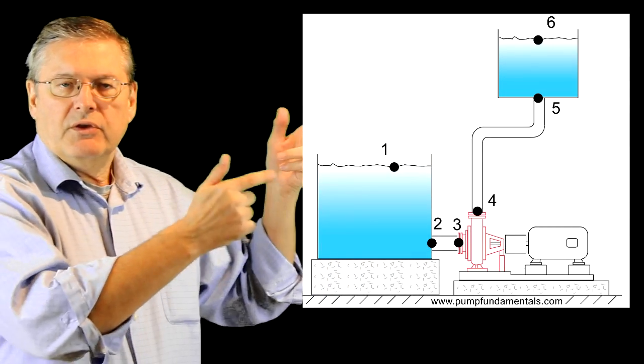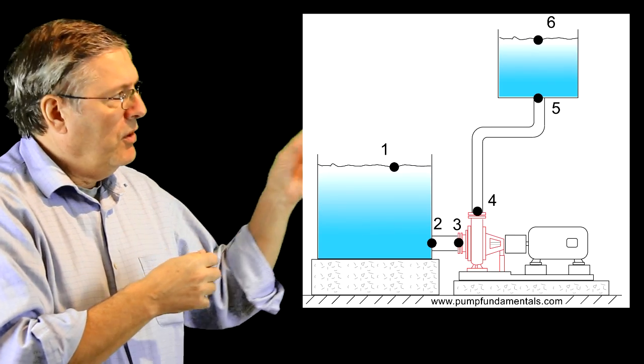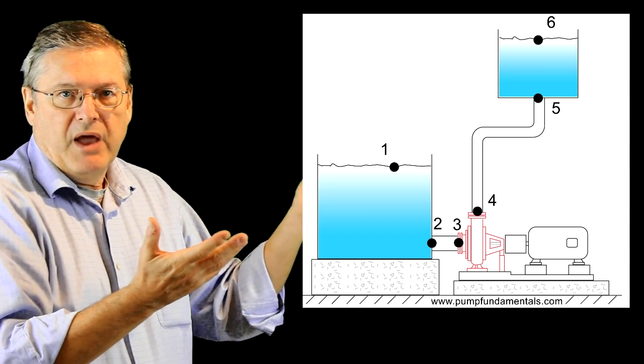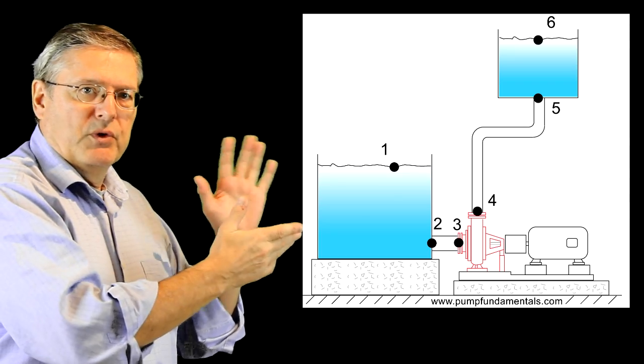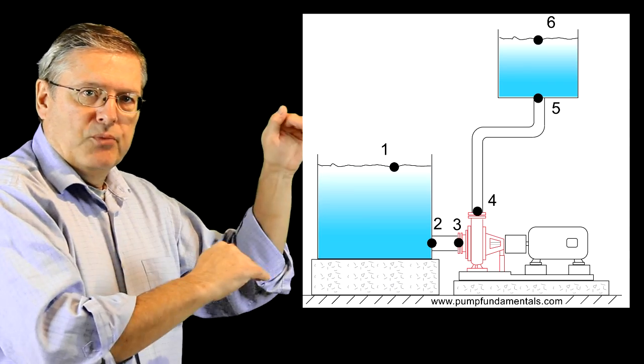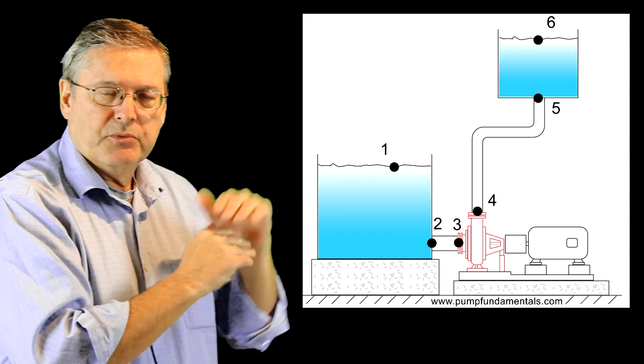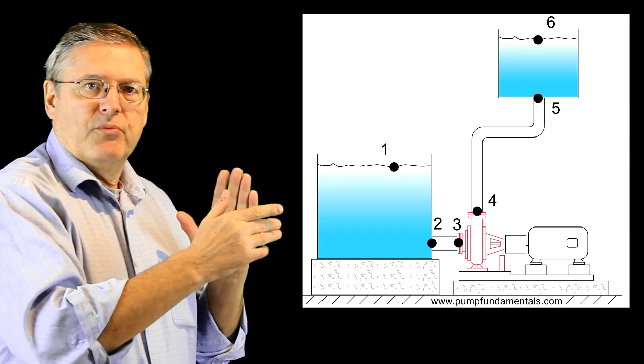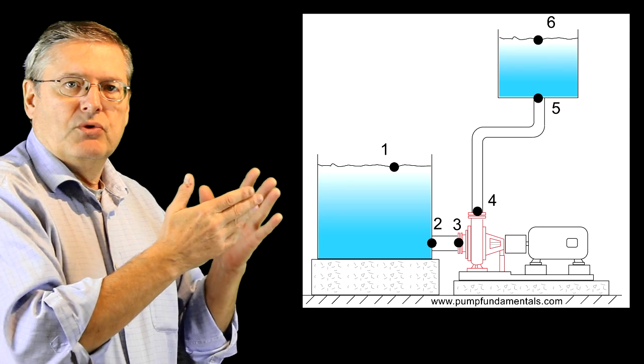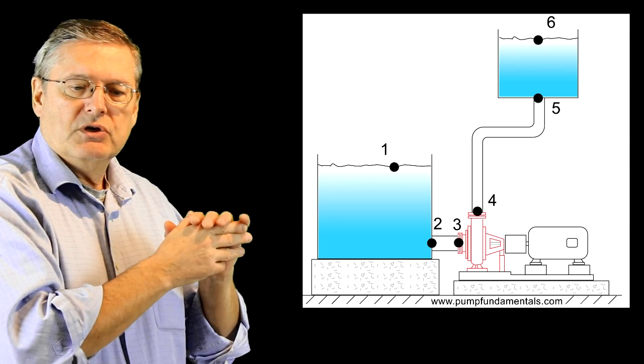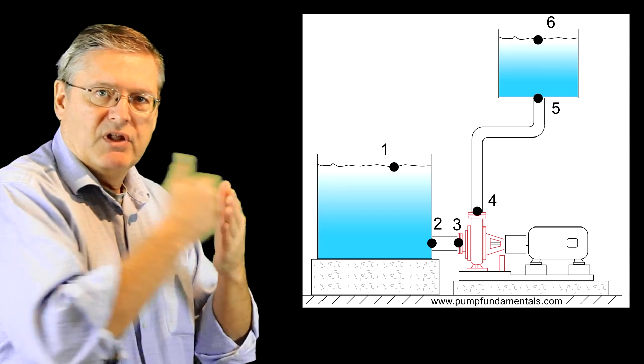We're going to look at all these points to discuss what the pressure or head would be. Point one is the surface of the tank — that's atmosphere, so the pressure is zero. Point two is right before the suction, at the outlet of the tank, so the pressure corresponds to the height of liquid there. Point three is right before the pump; between two and three we're at the same height, so three essentially has the same pressure as two.